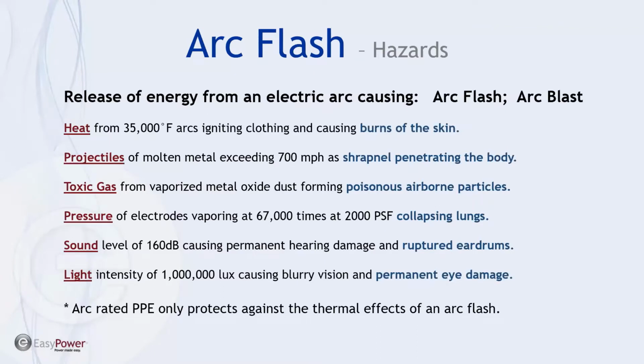Arc flash presents a number of hazards that can be harmful to humans, ranging from heat that approaches the temperature of the sun to toxic gas, pressure wave potentially because we have vaporizing metal that can throw projectiles 6 or 8 feet. It creates almost always a fairly significant sound level. One of the most common symptoms everyone complains about after being exposed to an arc flash event is how long their ears ring afterwards. And then obviously there's very intense light.